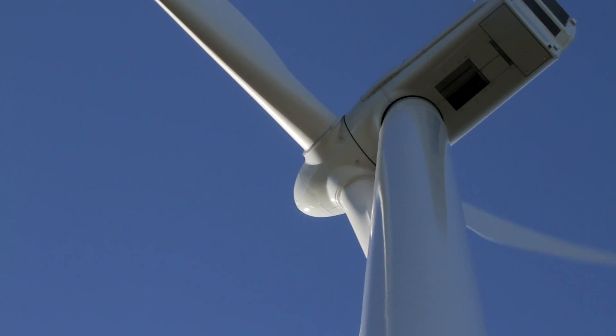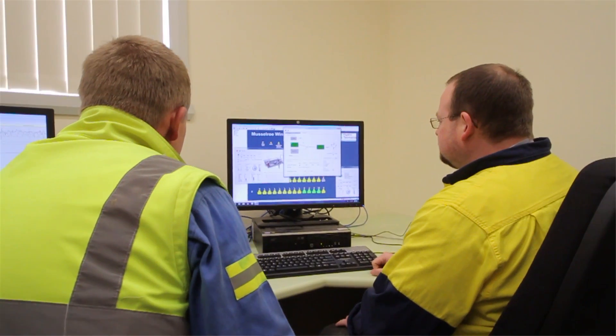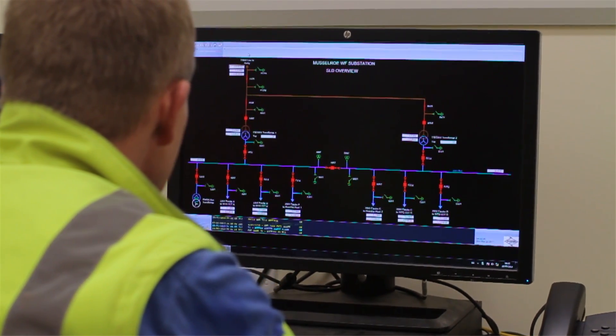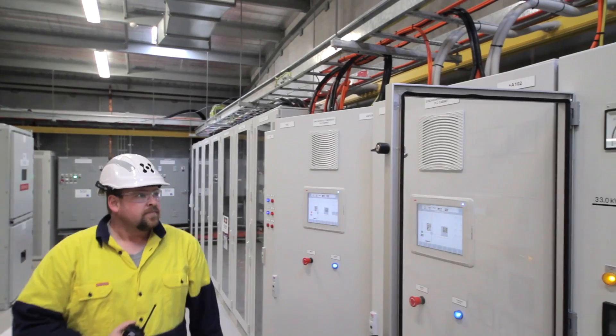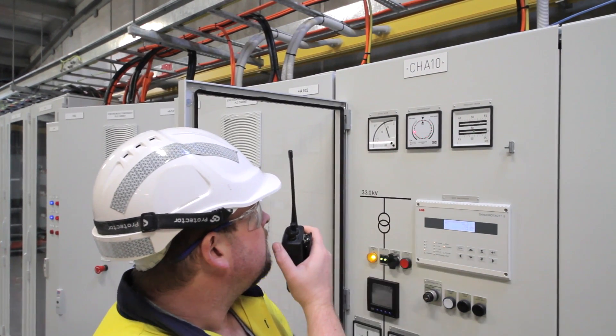The way the contracts have actually been structured, the wind turbines have requirements for several testing regimes. The first of these is a 168-hour reliability test, where we actually put the turbine to run uninterrupted for 168 hours, with a certain number of those hours being allocated for maximum generated output of the turbine. Based on that, the engineer signs off on whether the turbine has passed the reliability test or not. Thereafter, the turbine is available to be handed over to the developer for operation.